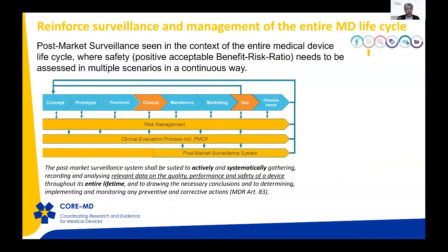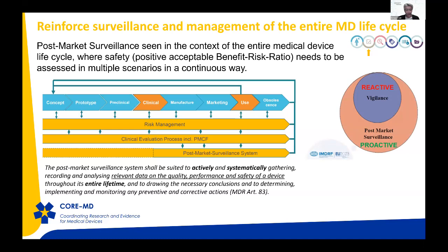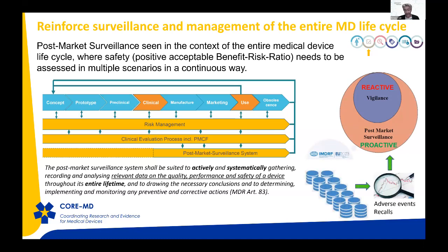In the concept of reinforcing surveillance, the MDR prescribes that different sources and actions need to be put in place by manufacturers along the medical device life cycle. And these actions include post-market surveillance, not only focused on a reactive approach, but also with a proactive focus on searching additional information from different sources. And among them, the different national databases of safety notices could be utilized in order to derive trends in alerts and adverse events in similar products on the market or for specific categories of devices.